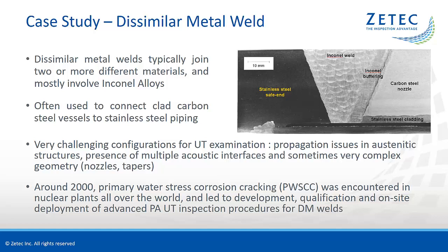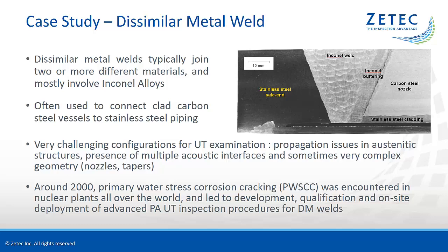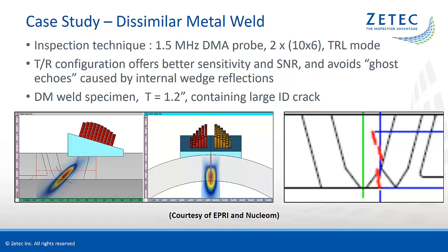Around the year 2000, a new damage mechanism called Primary Water Stress Corrosion Cracking, or PWSCC, was encountered in nuclear plants all over the world, and led to the development of advanced phased array inspection procedures for dissimilar metal welds. Zetec collaborated with EPRI in 2005 to formally qualify the first phased array procedure for in-service inspection of DM welds. Qualified inspection techniques are typically based on 1.5 MHz dual 2D matrix array probes generating L waves for better propagation in the coarse-grain austenitic material. The dual transmit-receive configuration offers better sensitivity and signal-to-noise ratio.